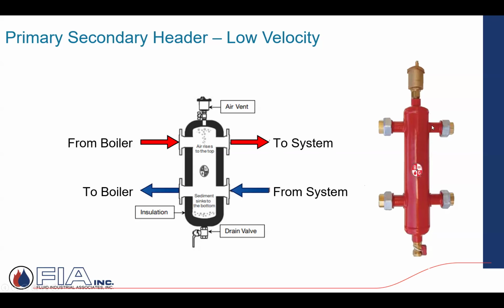And these devices, whether it be a small little 2 or 3 inch or come up to a larger, I think it's up to 6 or 8 inch, they'll come with a high capacity vent. So as this pumped flow coming from my boiler plant with hot water with air bubbles in it enters this area here, the velocity is such that the air is allowed to separate and vent out.